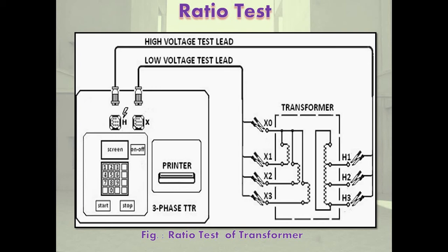Now, ratio test. Ratio test is also called the ratiometer or portable transformer method. So this is the ratio test method. This is the transformer under the check process. This is the high voltage test lead, this is the low voltage test lead, this is a printer, and this is a 3-phase TTR. Now this test can be done using a calibrated voltmeter, but it is preferable to do it by a special ratio testing apparatus called a ratiometer.